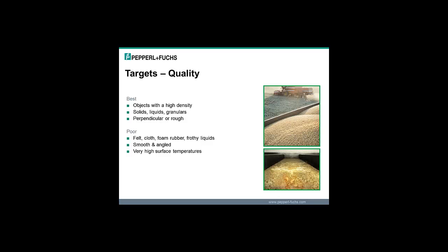And then very high surface temperatures. If you're looking at steel, molten steel, things like that, with ultrasonics, that radiant heat that comes off of the product will diffuse the sound waves and pretty much render the product undetectable. For diffuse mode, Thru-Beam mode, it wouldn't matter.